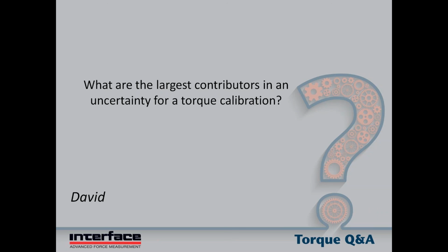When you have the two sensors in line for a comparison calibration, there's the assumption that they're both seeing exactly the same torque. If you're, say, not using appropriate couplings, then you may have a lot of bending or other extraneous loading in the system that really prevents the torque from being identical in the two devices under test. And in torsion, that's more difficult than in, say, force calibration. So I think it's one of the bigger factors, but it's not necessarily well understood.